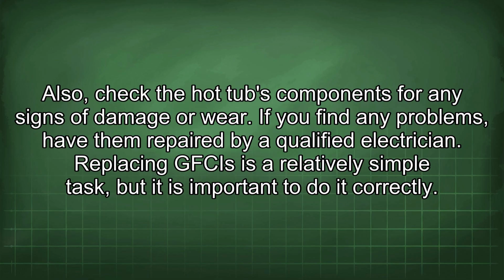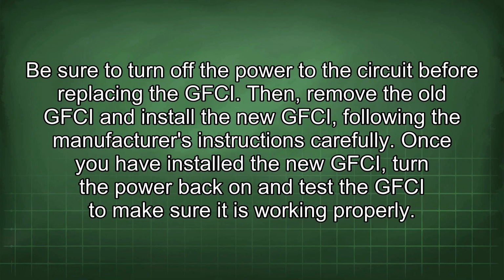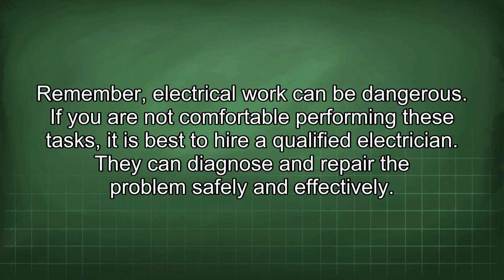Replacing GFCIs is a relatively simple task, but it is important to do it correctly. Be sure to turn off the power to the circuit before replacing the GFCI. Then remove the old GFCI and install the new GFCI, following the manufacturer's instructions carefully. Once you have installed the new GFCI, turn the power back on and test the GFCI to make sure it is working properly. Remember, electrical work can be dangerous. If you are not comfortable performing these tasks, it is best to hire a qualified electrician. They can diagnose and repair the problem safely and effectively.